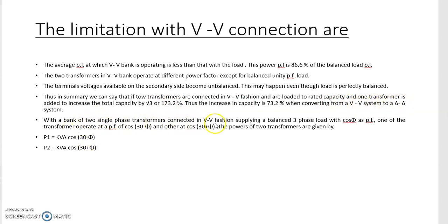With a bank of two single phase transformers connected in V-V fashion, supplying a balanced three phase load with cos phi as power factor, one transformer operates at cos 30 minus phi and the other at cos 30 plus phi. So, the power for the two transformers becomes KVA cos 30 minus phi and KVA cos 30 plus phi.